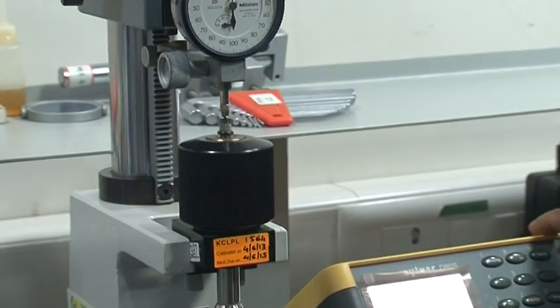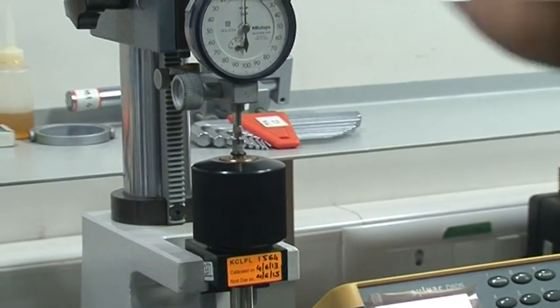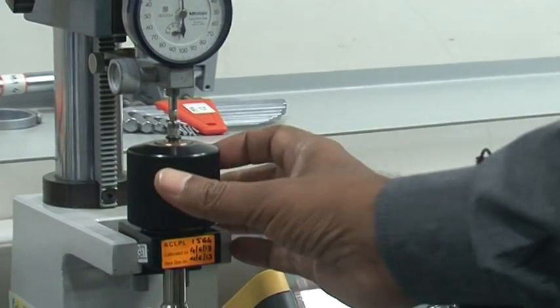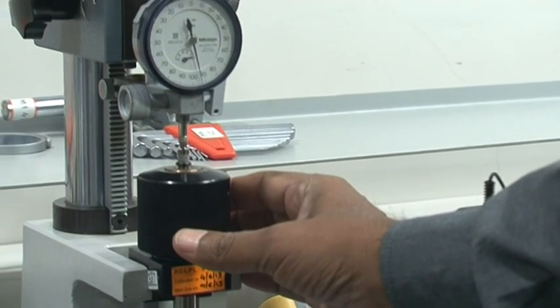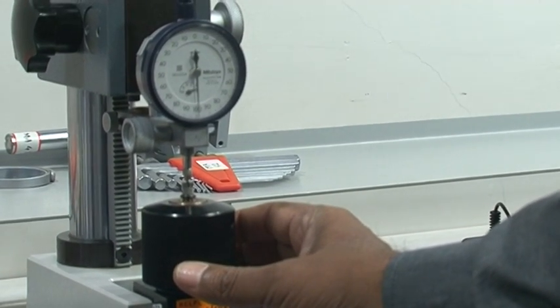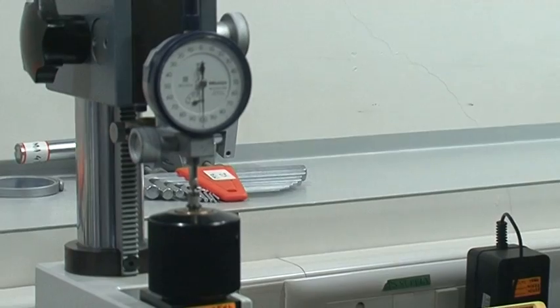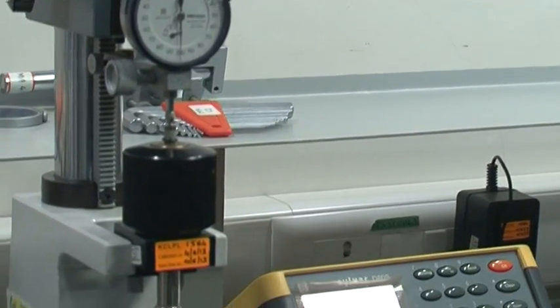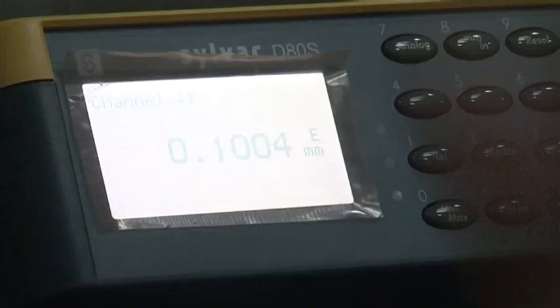First we set the dial at 0 and then the DRO reading is also set to 0. Then rotate the spindle of the DCT slowly to get the desired reading on the dial and note the corresponding reading observed on the DRO of the DCT. In this way we have to take further readings at several points of the dial as recommended by the standard.